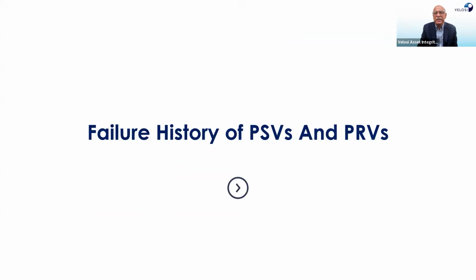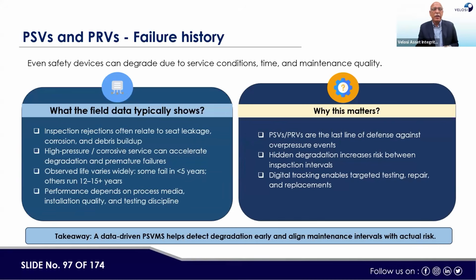Now, failure history of the PSVs and PRVs, so there is a big history. These PSVs can fail if they are not handled properly. Here, what does field data typically show? Mostly, inspection rejections relate to seat leakage, corrosion and debris buildup. This is the main problem. Then high pressure corrosive service can accelerate degradation and premature failure. Then observed life varies widely. Some fail in less than 5 years, others may cross a minimum of 12 to 15 years. Performance depends on process media, installation quality, and testing discipline.